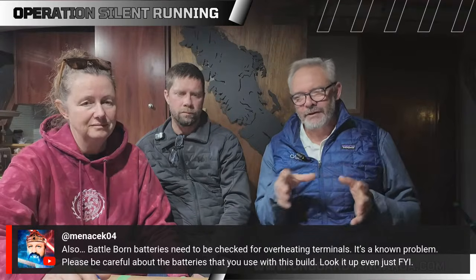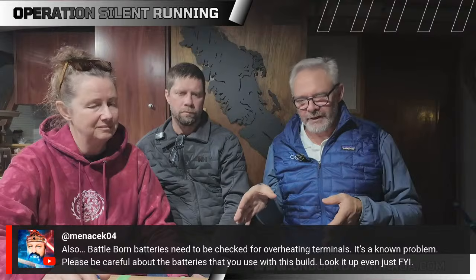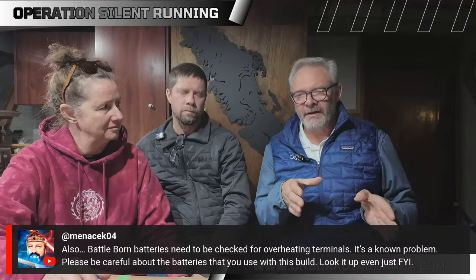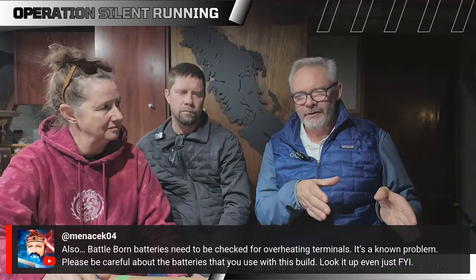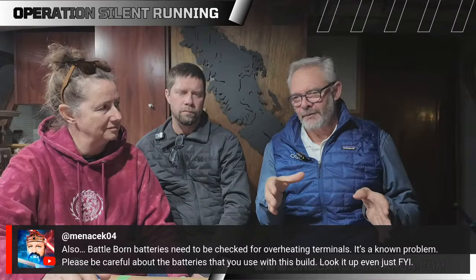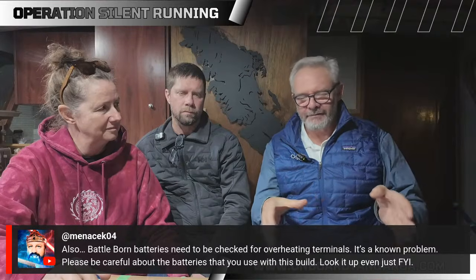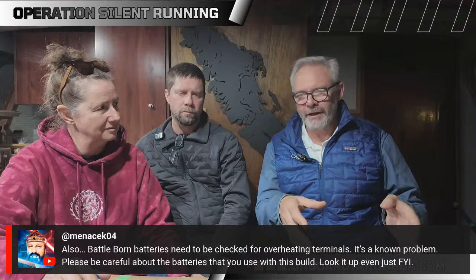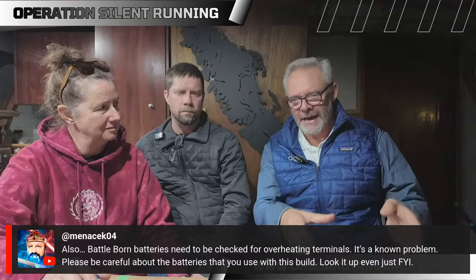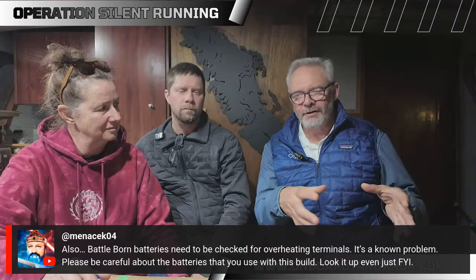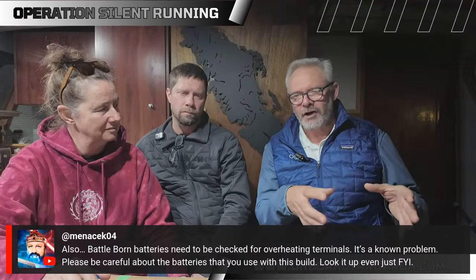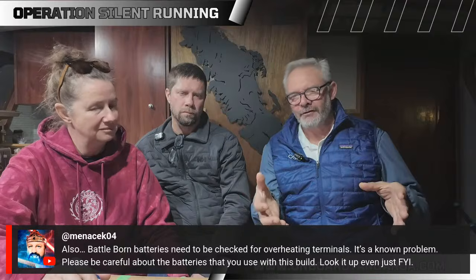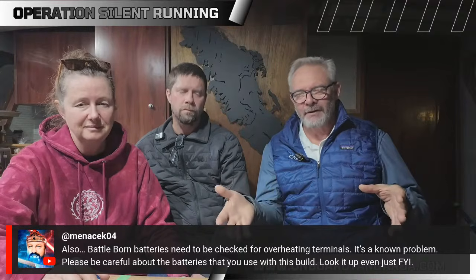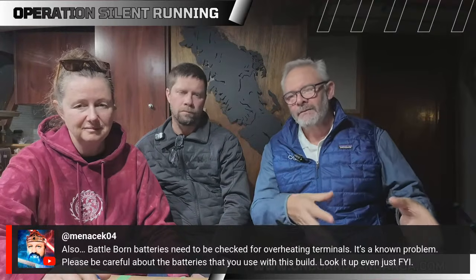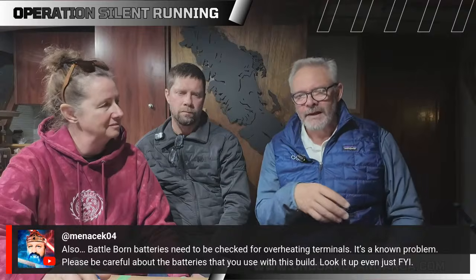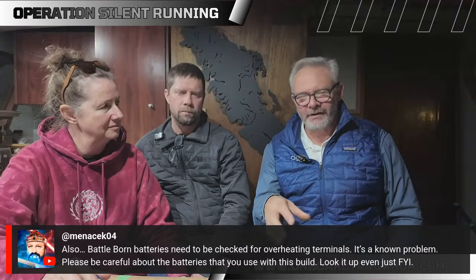So when we do these installations, we almost always use 1C as the charge rate. In this case, we'll actually have almost a 0.5C, because we're going to have somewhere between 340 and 400 kilowatt hours of battery and roughly 200 kilowatts of charger. If we only put in the original concept of 200 kilowatt hour batteries, we'd be charging in 1 hour, a 1C system. In this case, we're probably going to end up at 0.6, 0.5.